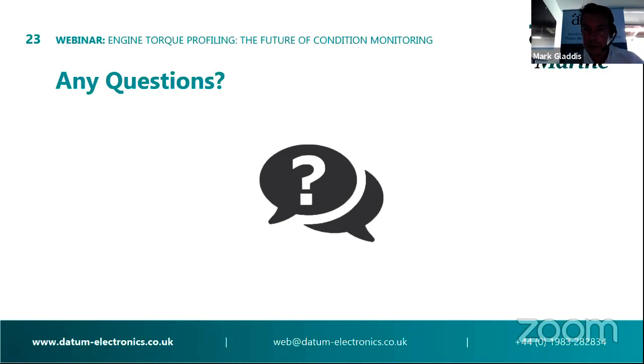If we're measuring torque and thrust, yes, we use 2 gauges, one at 45 degrees. For torque measurement alone, you can use 1 strain gauge, but we always put 2 down, one for redundancy should there be any issues with the main sensor. So it's 1 per channel, meaning you can have 1 for torque and 1 for thrust.